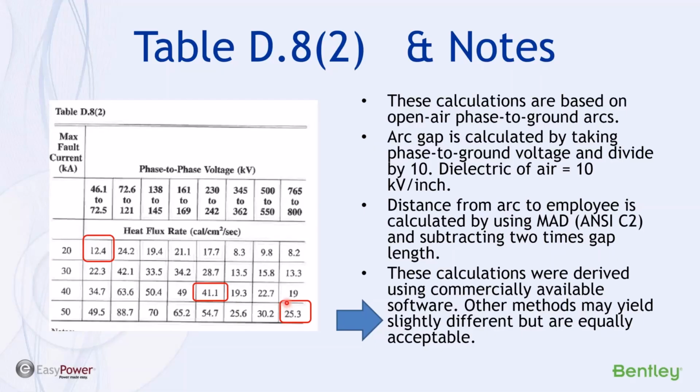And that's the advantage of using EasyPower to do this. The point I made, and it's more detail than you want to hear, is I picked three different areas and worked through the directions on what these calculations are, including the air gap as described in the notes. And I get a one-for-one correlation between the results we see here and the results that were published in EasyPower.